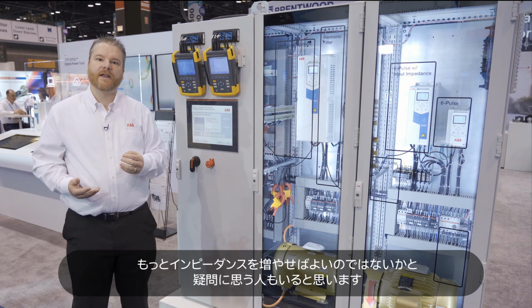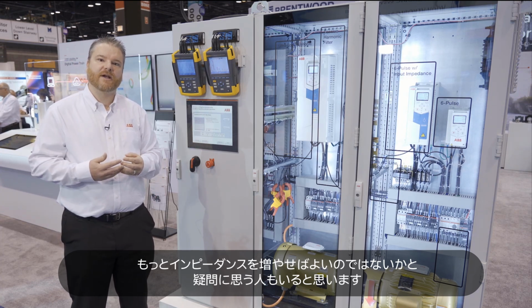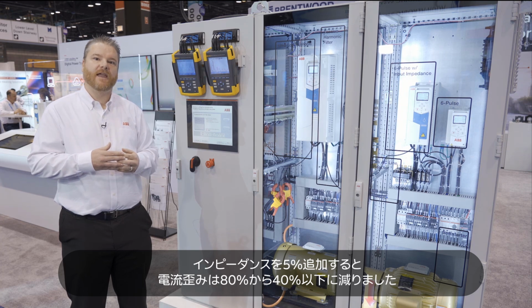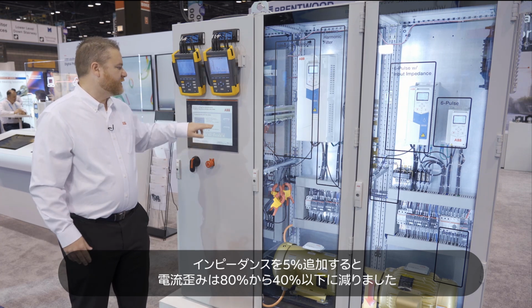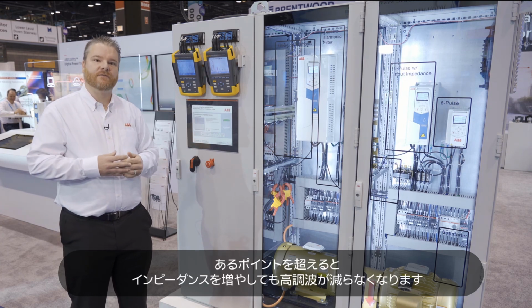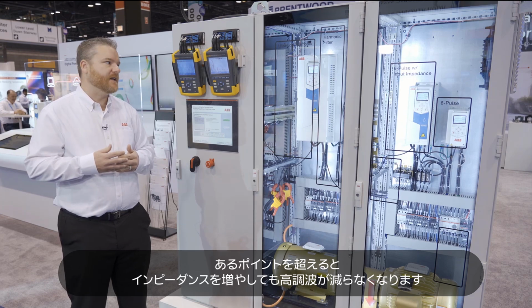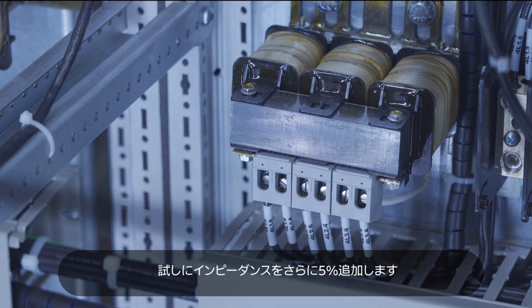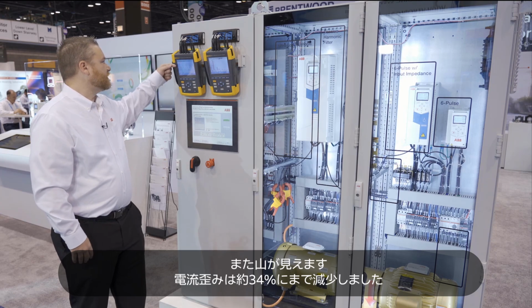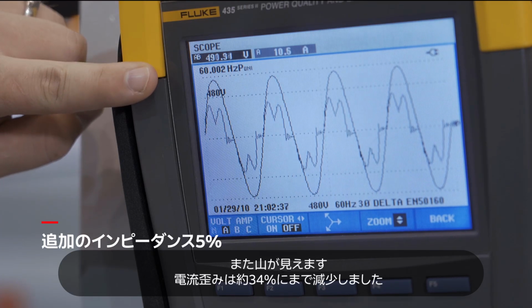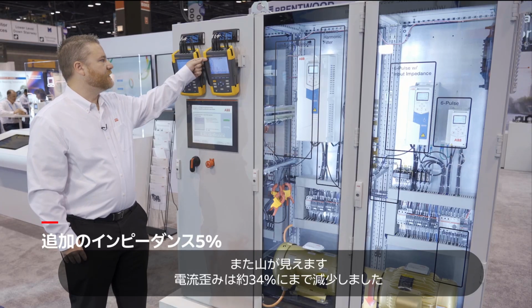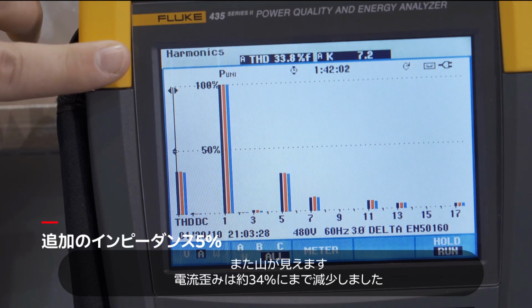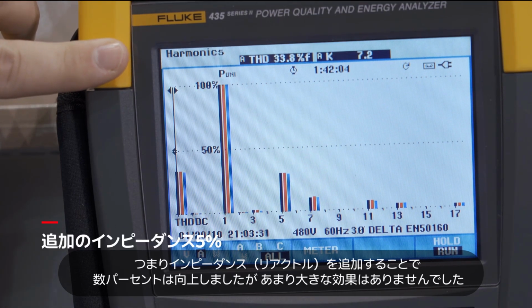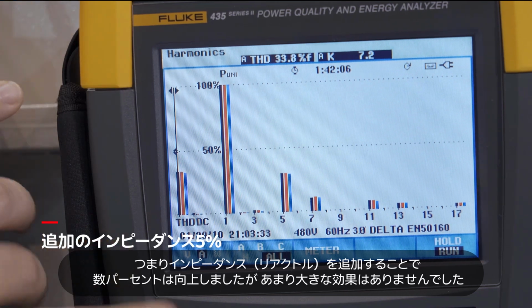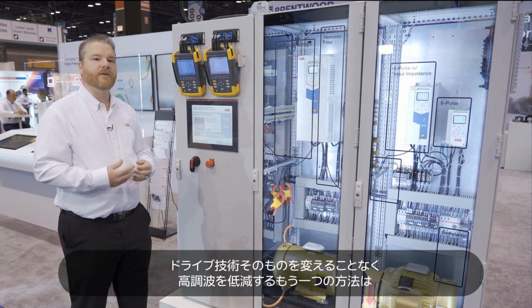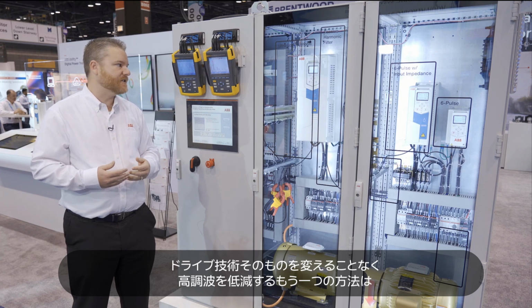Some folks will ask, well, why not just continue adding more and more impedance in the drive? You added 5% into it, you cut it from 80 to less than 40. There's a certain point where you just don't have the advantage of getting reduced harmonics by adding more and more impedance. So I'm adding another 5% as a demonstration. And you can still see I have the bunny ears going on, and I'm only down to roughly 34% current distortion. So I lost a couple extra percent by adding that reactor in there, but really there wasn't a whole lot of value there.